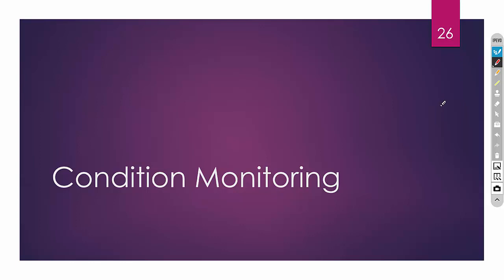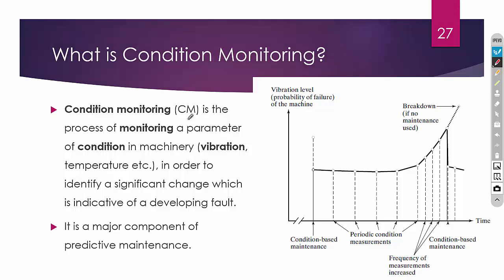In this lecture we are going to discuss condition monitoring. Condition monitoring is the process of monitoring a parameter of condition in machinery in order to identify a significant change which indicates a developing fault. We monitor the system's performance 24/7 based on various parameters. For example, we can monitor temperature — if we have a safe limit of 70 degrees Celsius and the temperature exceeds that limit, it means there is some fault in the system that we can rectify.